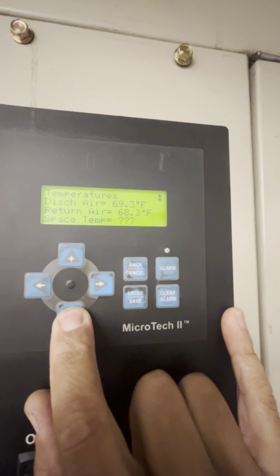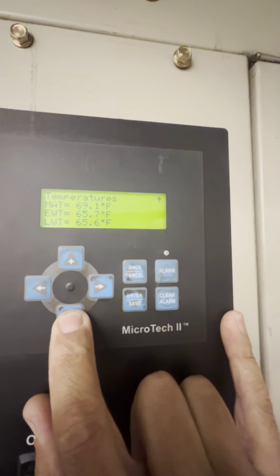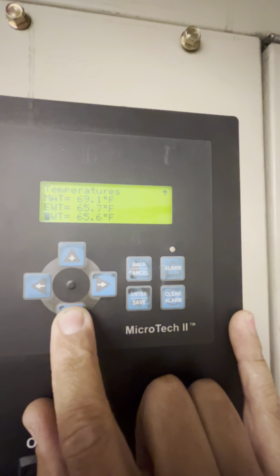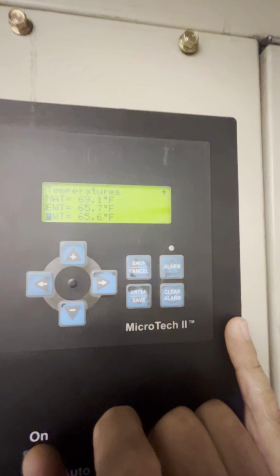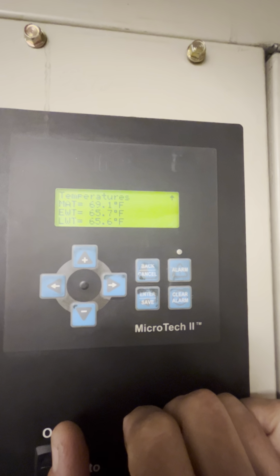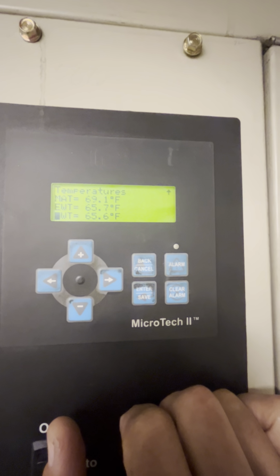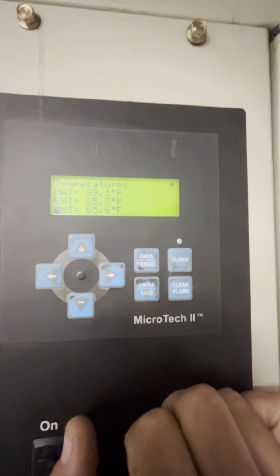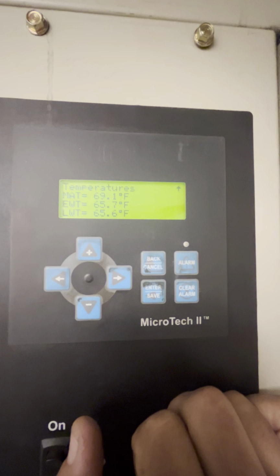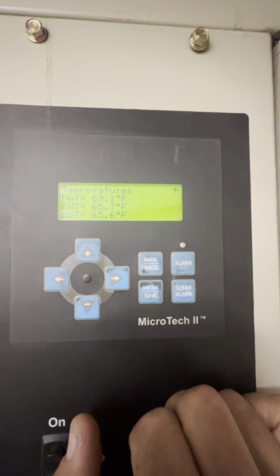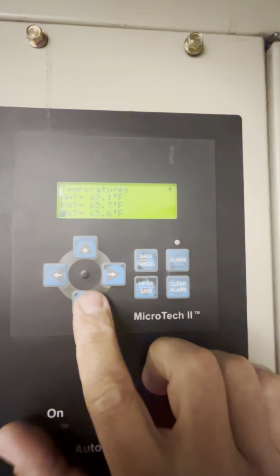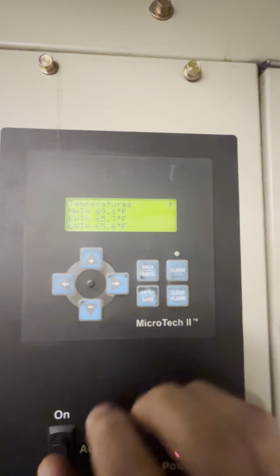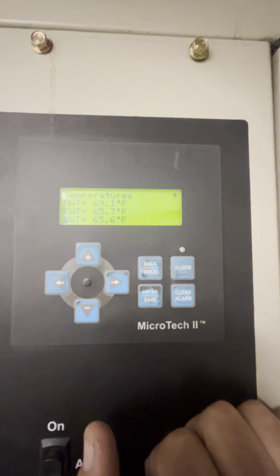Return air is the air coming back from the offices to the unit, so that gives you an idea of your temperature spread there. As you go down, you get your condenser water temperatures. Right now it's cool because it is nice and cold outside. In the summertime, those temperatures will get into the 80s, sometimes 90s. You don't want to go much above 90. That'll start causing high pressure alarms on your compressors, so just continually check that and make sure those are within the 80s. If they get out of whack, you need to check your cooling tower for potential issue.